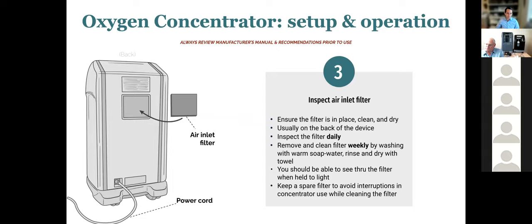So next up in the setup of a concentrator, you're going to want to inspect the air inlet filter. Make sure the inlet filter is, first of all, present. It's not uncommon that these might be removed and not replaced. There may still be a plastic grill on the back and you might not notice that there's a piece missing. So always make sure that there's an air inlet filter on the back. It usually looks like a black piece of foam, which we'll show in a little bit.